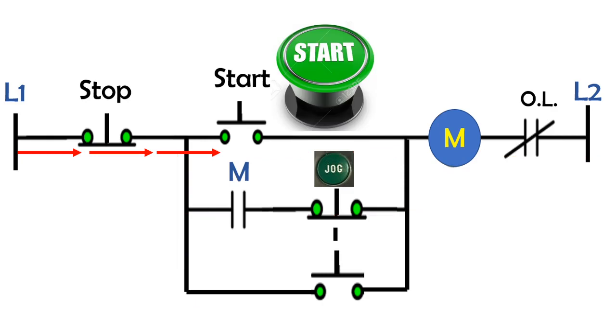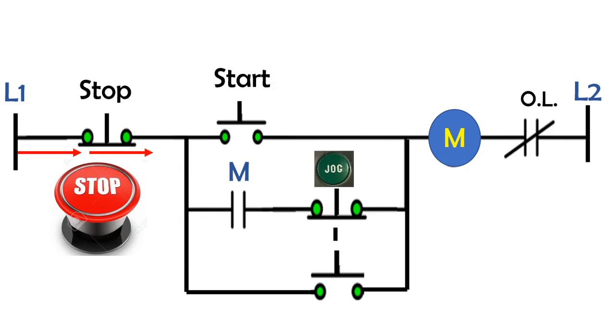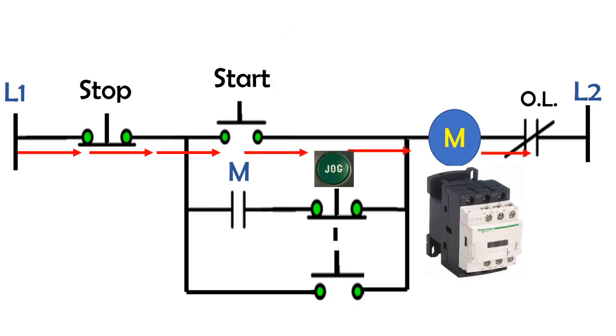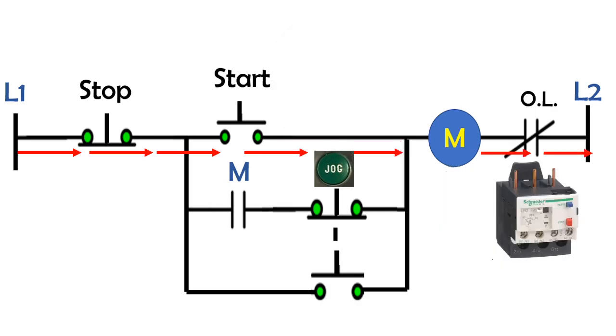When you press the start button, current flows from line one through the stop pushbutton that is connected in series with the circuit, through the start pushbutton that is connected in parallel, through the magnetic contactor and overload relay.